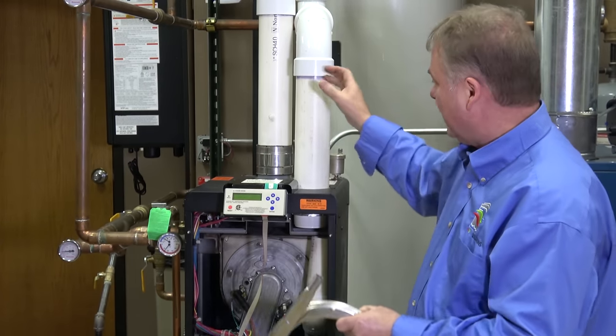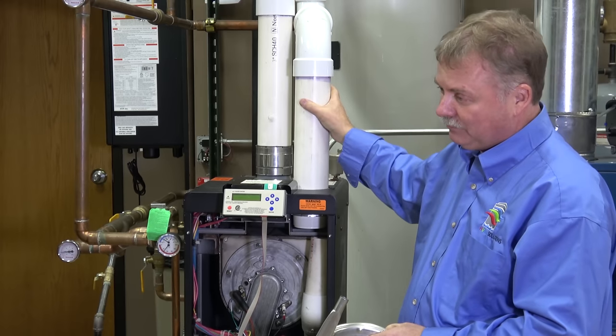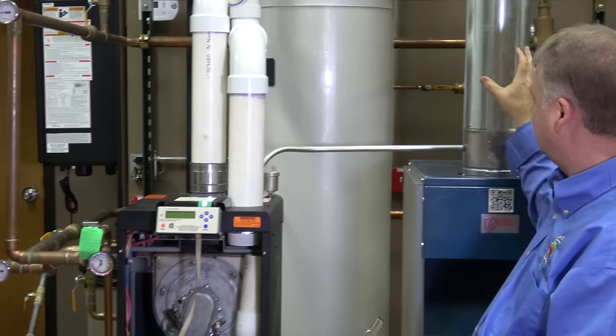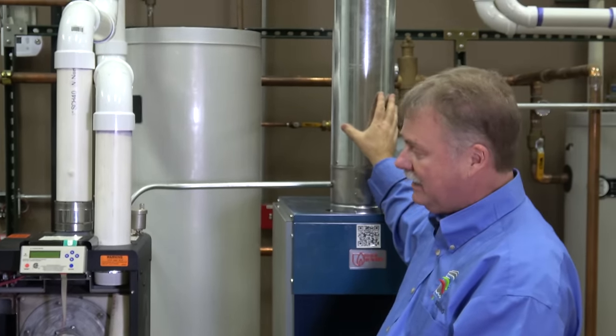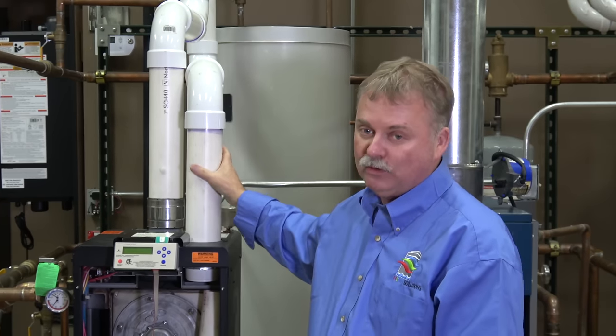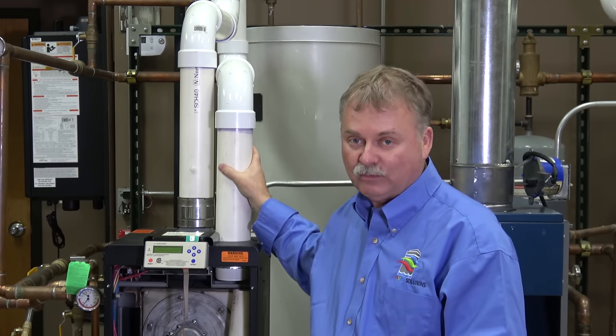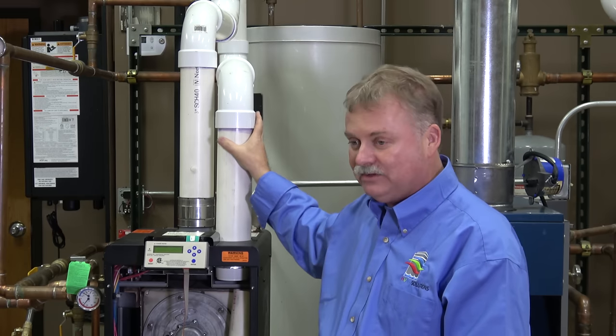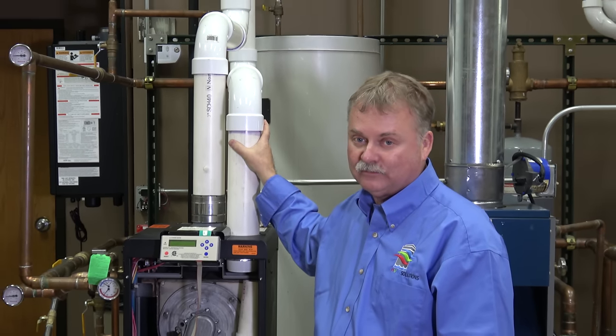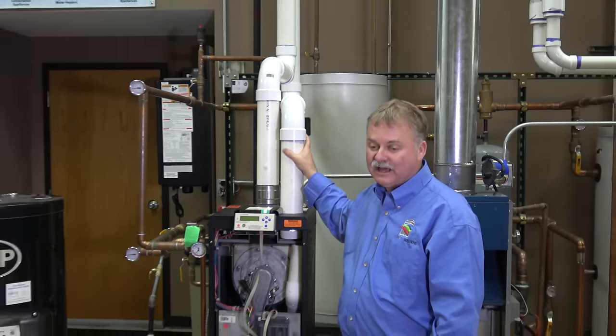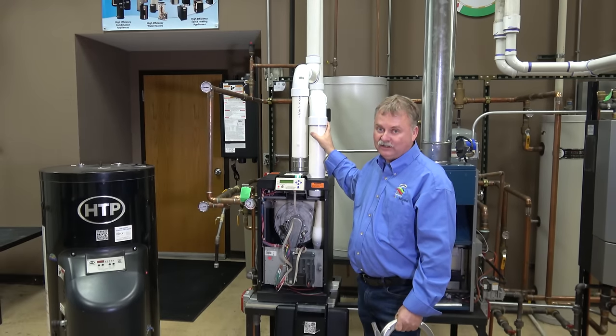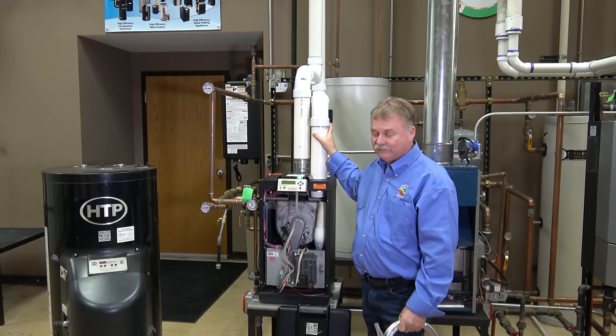As you can see, the difference here, over here we have cast iron, and here we have steel. This is a non-condensing boiler. This boiler condenses at the right water temperatures. That means the flue temperature is cooler, so a lot of times we can use PVC for the venting material.